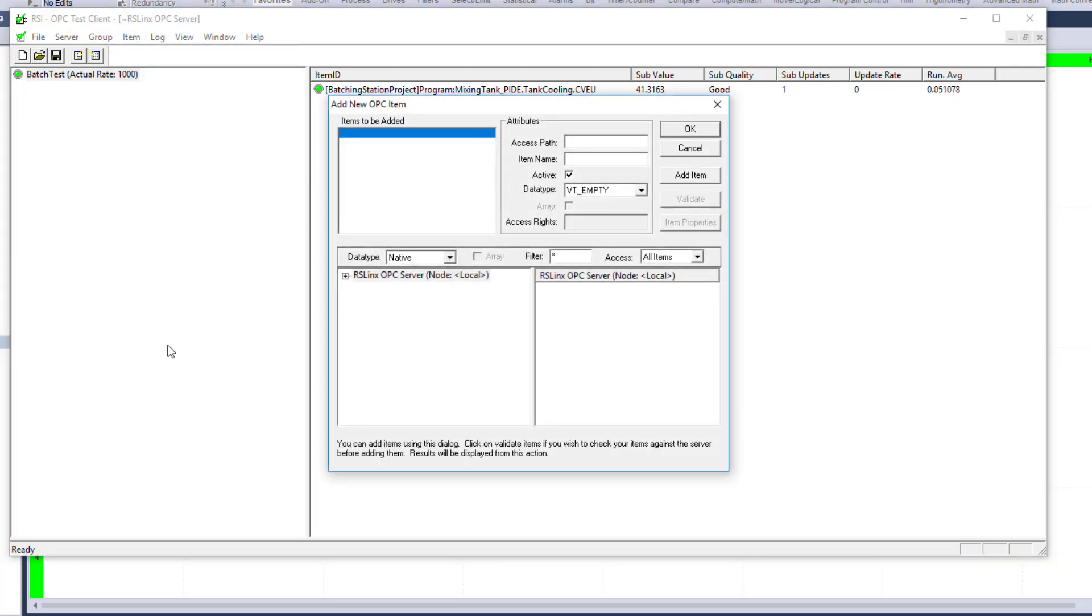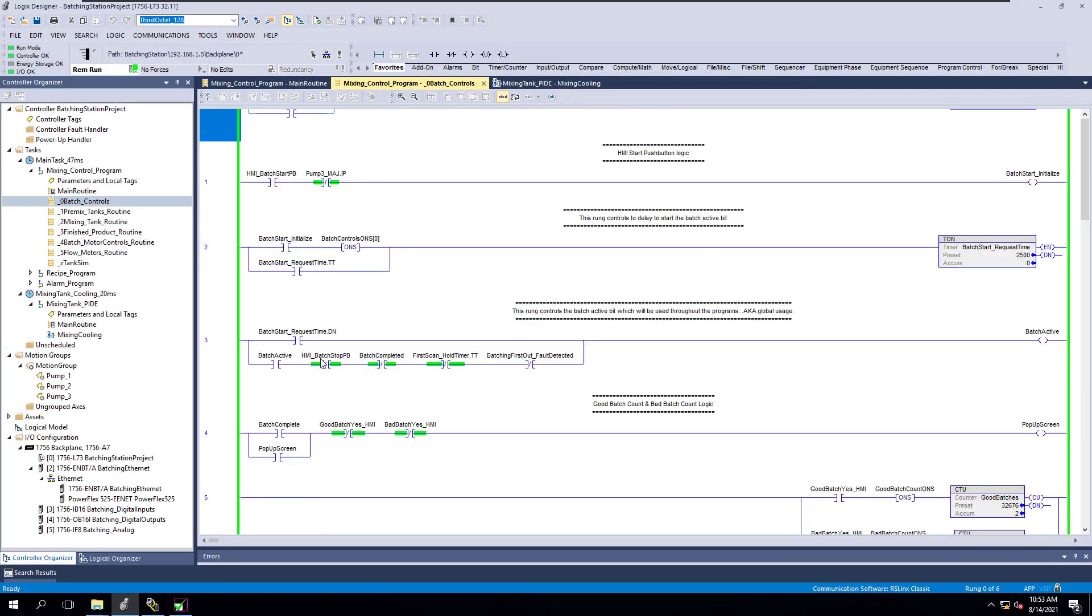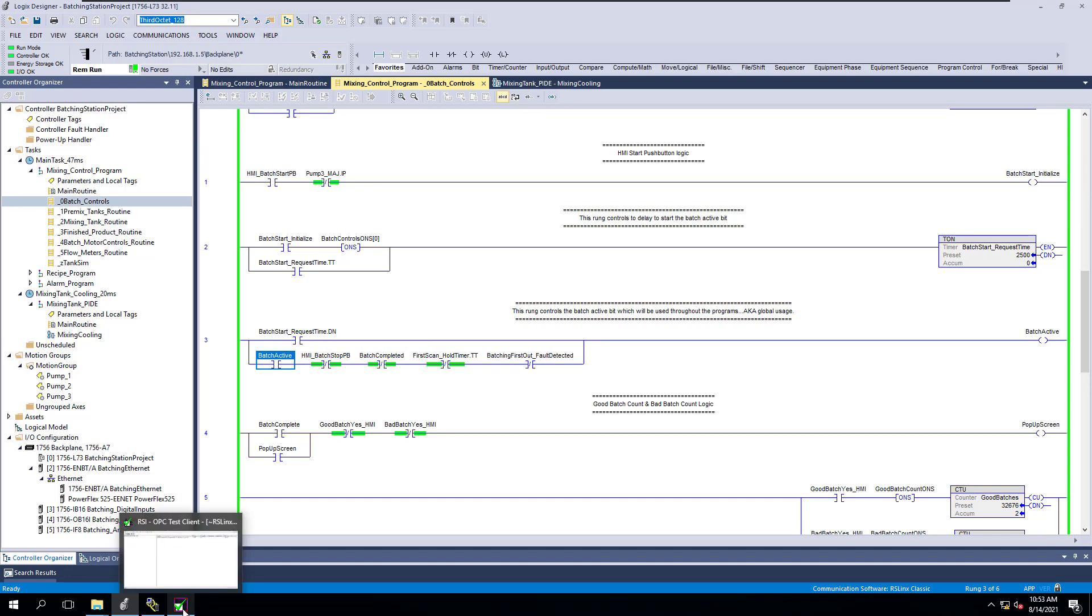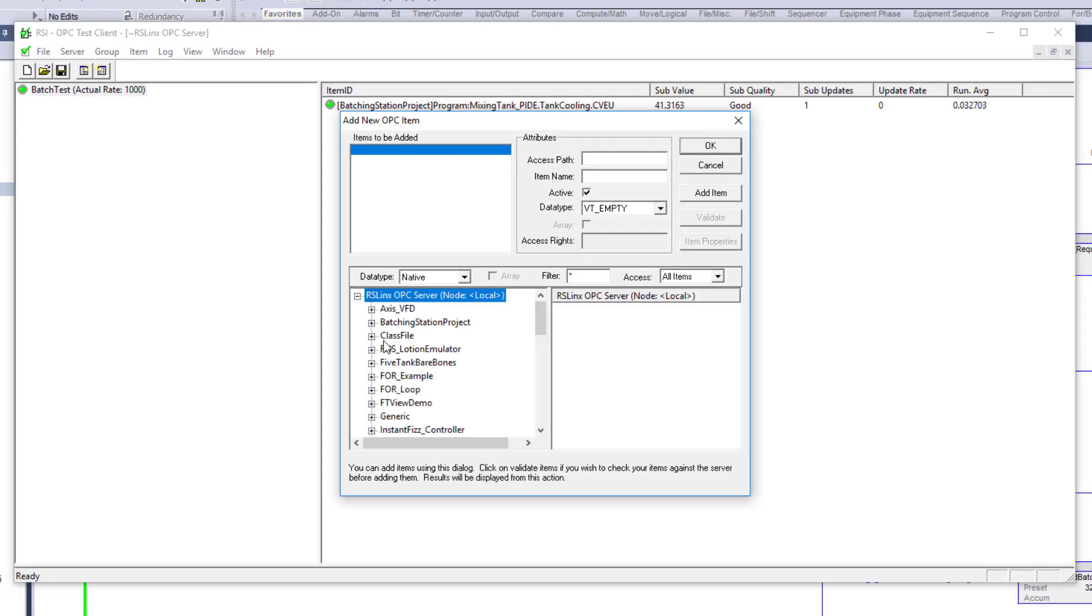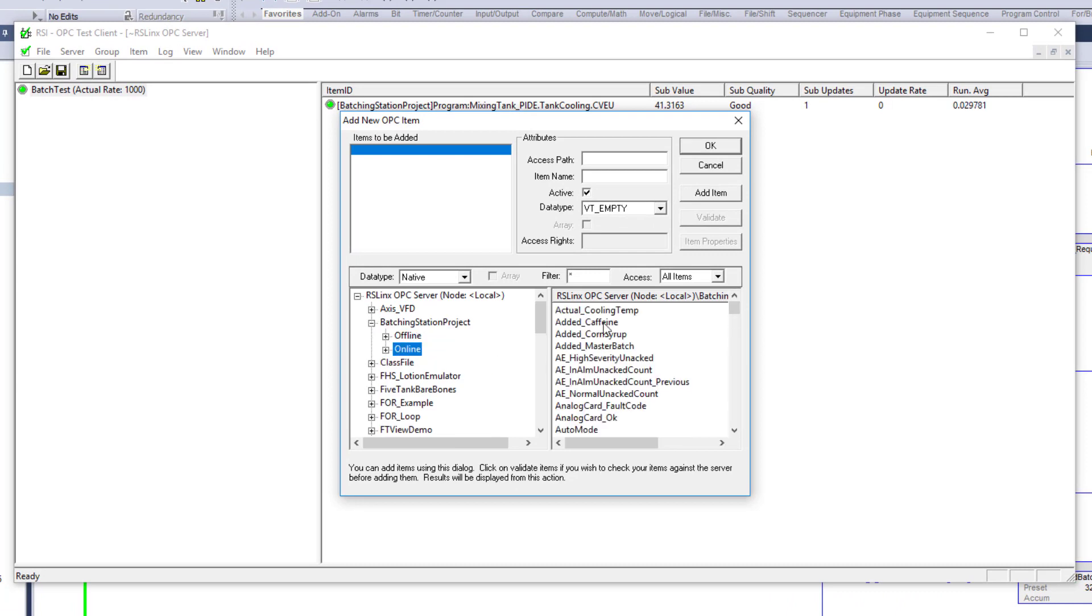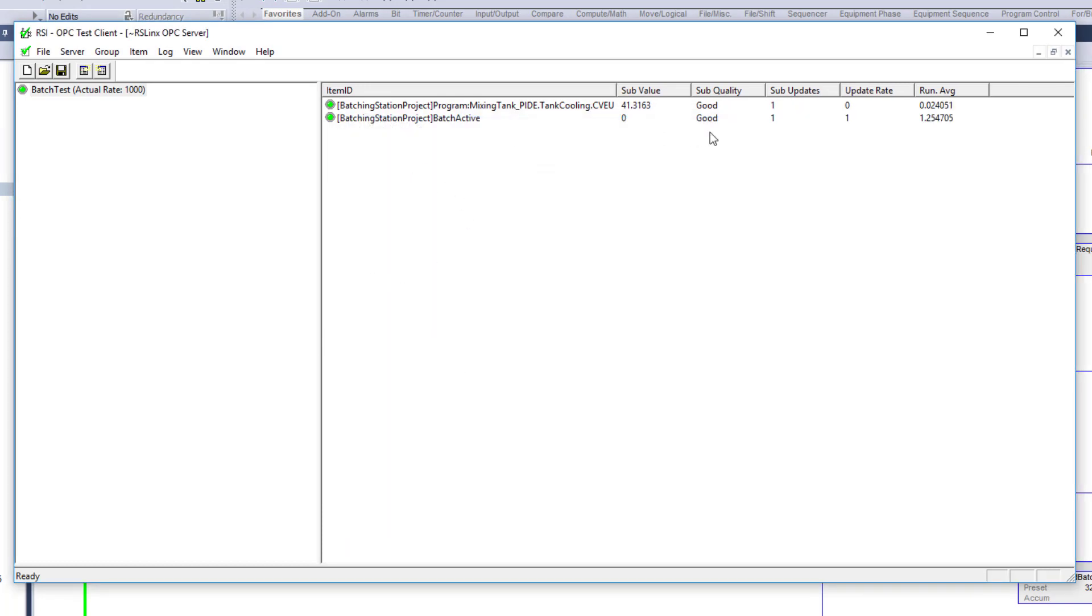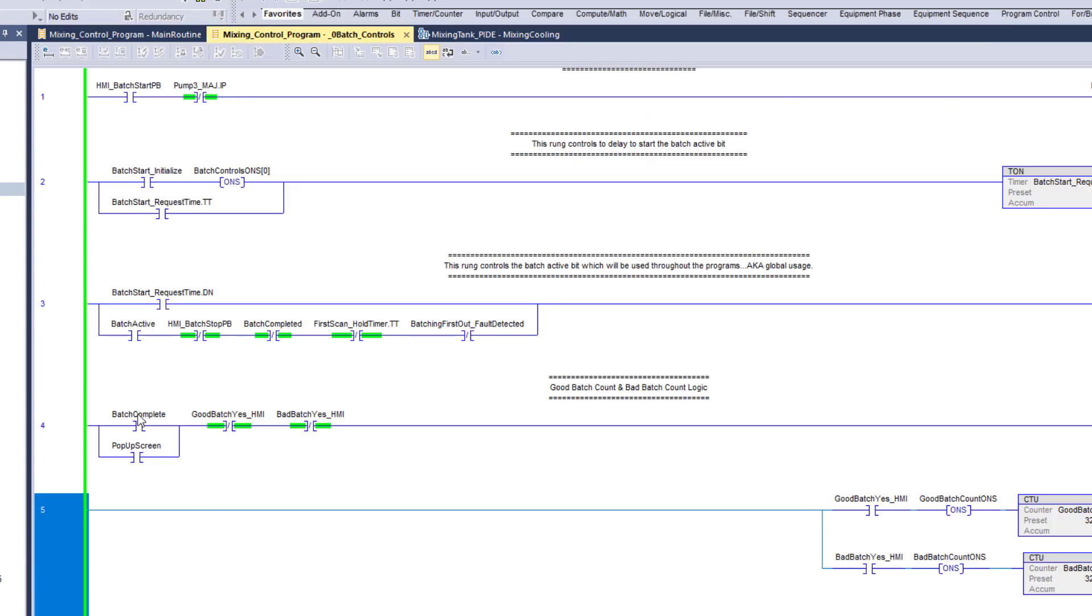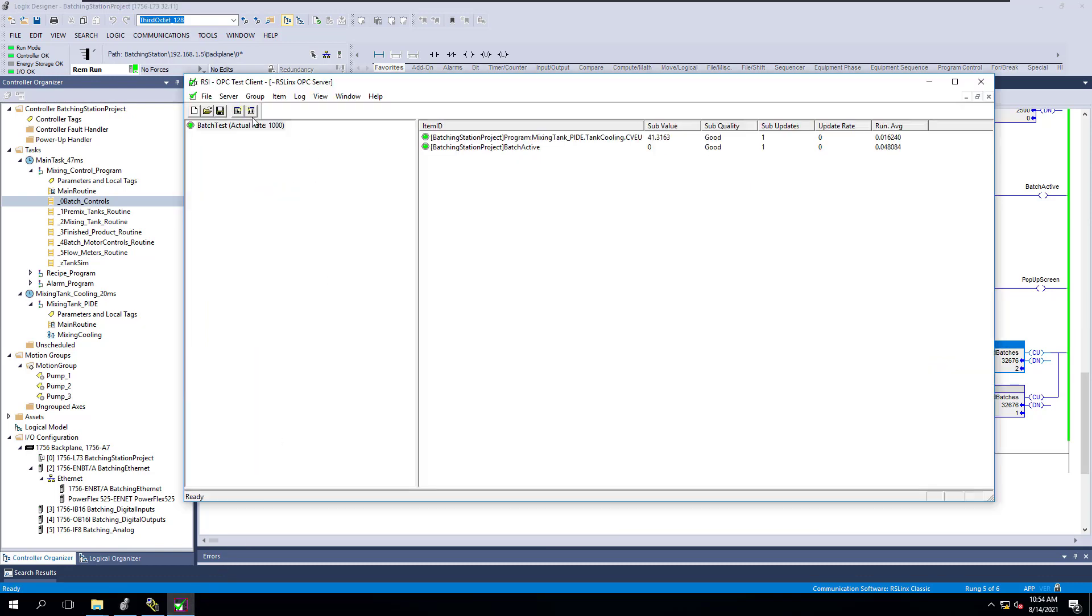Now, again, you can add some more stuff in here. So let's add something a little bit less complex. Let's go to batch controls. Let's do batch active. So let's just grab batch active. In this case, we'll come over here. We'll go over here to online, and we'll get batch active. We'll add that tag, add that up to it, and now we have batch active. Now, batch active is currently not on, so we have a value of zero. If I were to make that batch active high, then it would come on. In this state, we can actually look, and let's just look at good batches, and we can look at the ACC of the good batches.